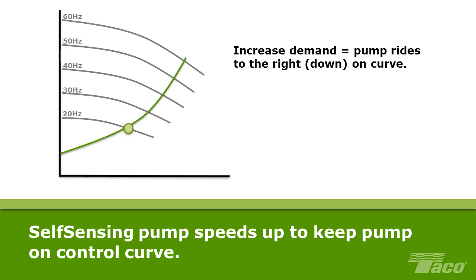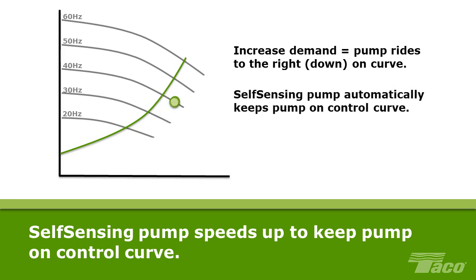Here's a pump curve to illustrate. As demand increases, the system requires more flow. As the rate of flow increases, head decreases. The pump begins to ride to the right on the pump curve. However, as the system curve changes, the self-sensing pump automatically responds, in this case increasing speed, to keep the pump on the programmed control curve.